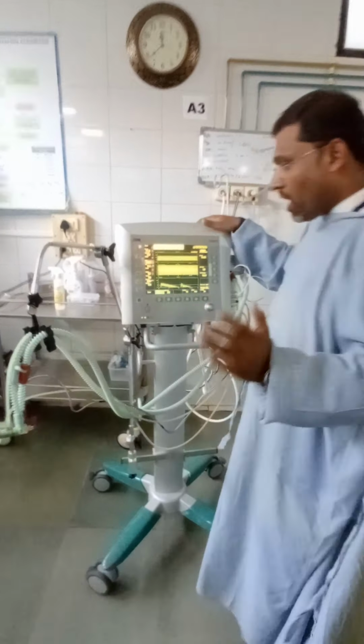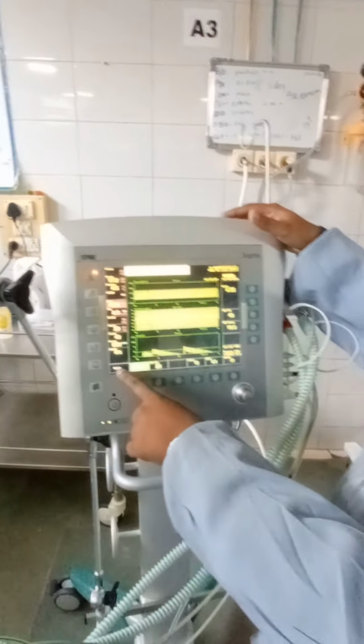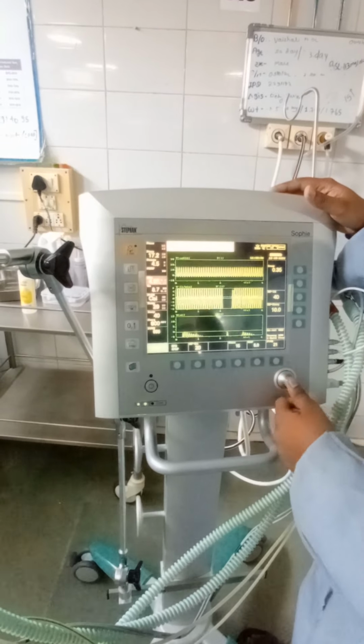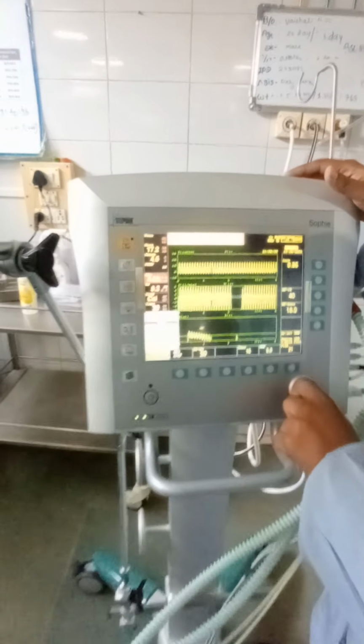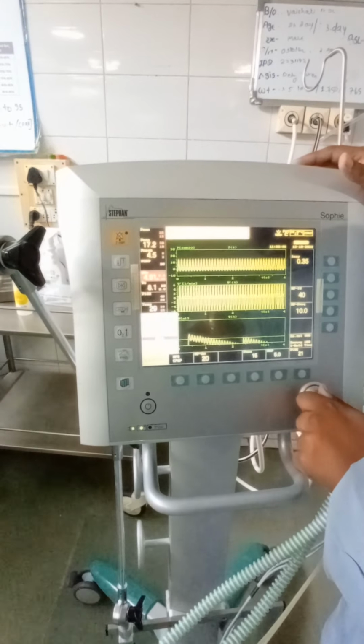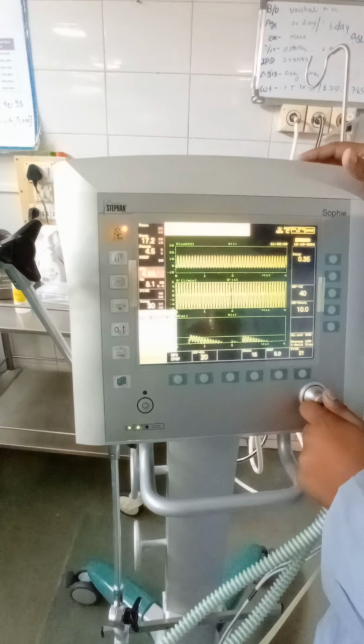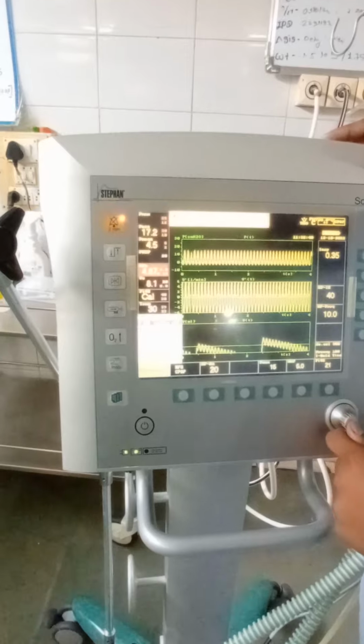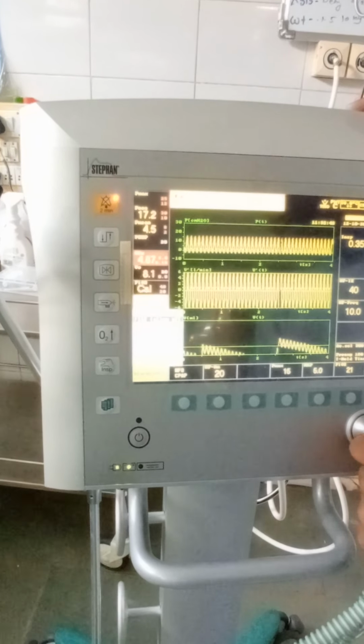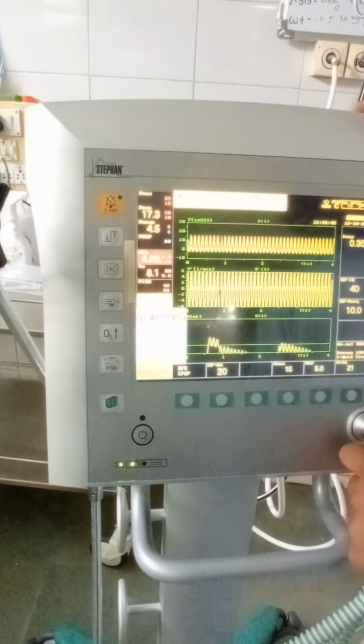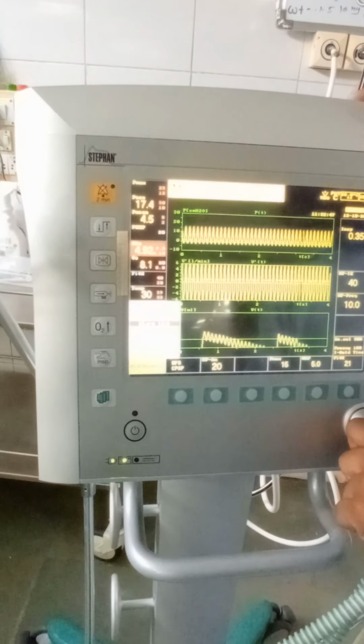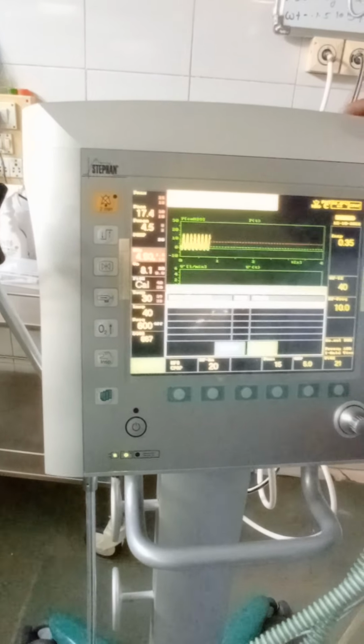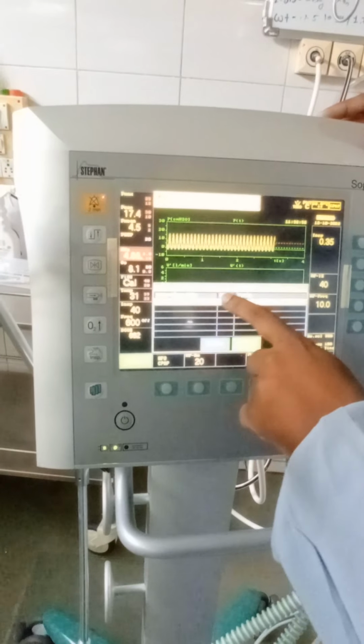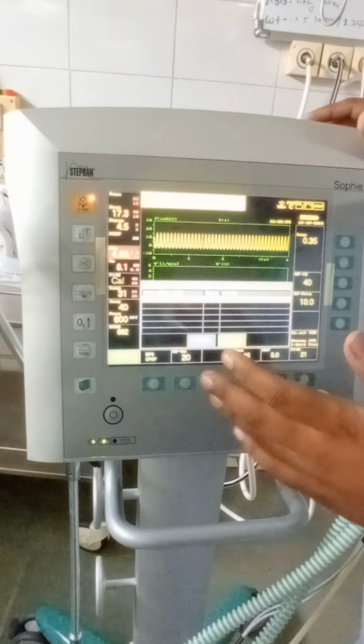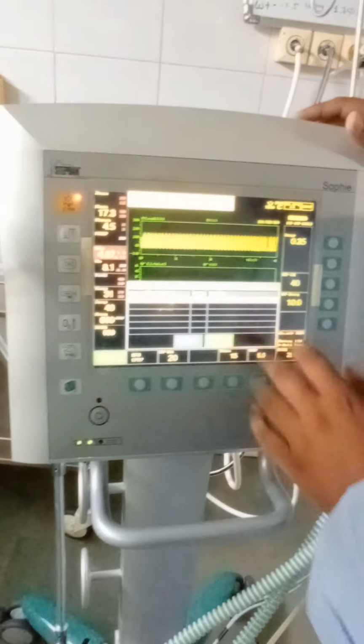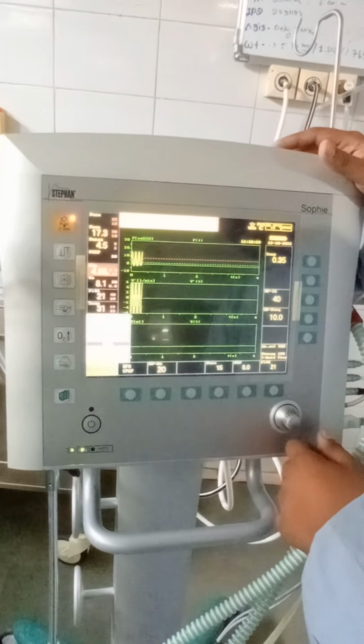Come close. Now how to adjust the alarms? So you can observe this menu. You have to go into the menu. You just go to the alarm limits. Suppose I want to change the FiO2 alarm, right? So this is nothing but FiO2, right? On off. I can make the FiO2 on off from here. Right. Now I am in the alarm list. Okay, you can observe different alarms which occurred during the ventilation. You can reset. You can delete the alarms from this end.